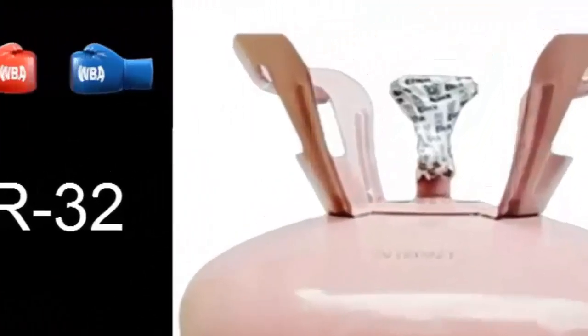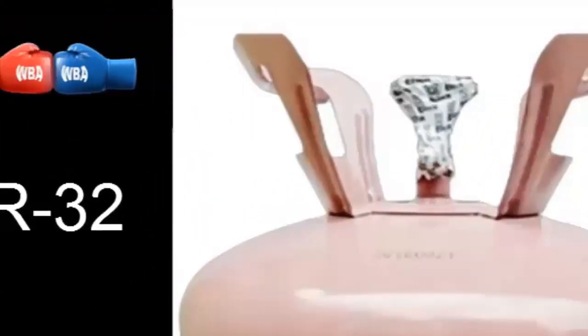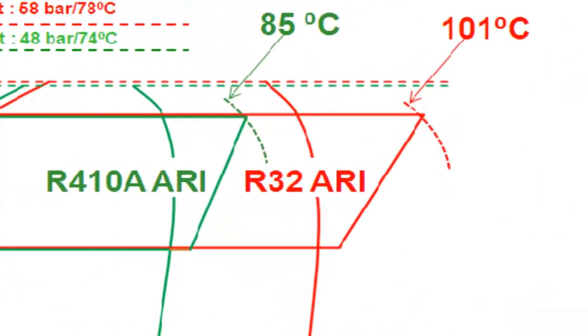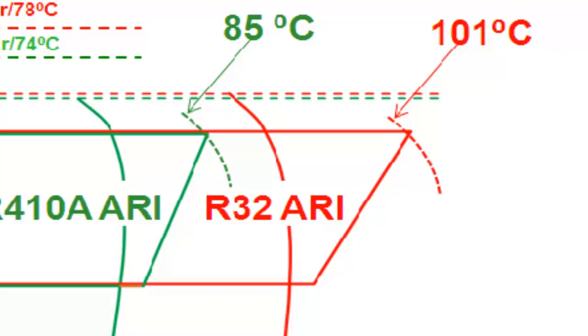R32 exhibits a higher temperature at the compressor outlet compared to R410A. Therefore, it is crucial when working with R32 to use high viscosity POE oils, ensuring greater viscosity stability as temperature changes.